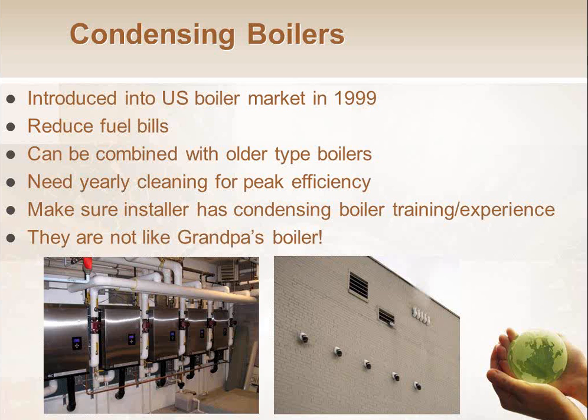Condensing boilers, by definition or by default, are pretty much always 90% efficient and greater. To get something to go into the condensing mode, you're pretty much in that realm. There are some folks that may have an 88 or 89% boiler that's kind of a partially condensing boiler, but pretty much 90% and above is condensing, 85% and below is non-condensing, and anything in the middle there is just kind of an oddball, and not many manufacturers play in that arena because it's kind of hard to know if something's going to condense or not condense at 82, or excuse me, at 88%.